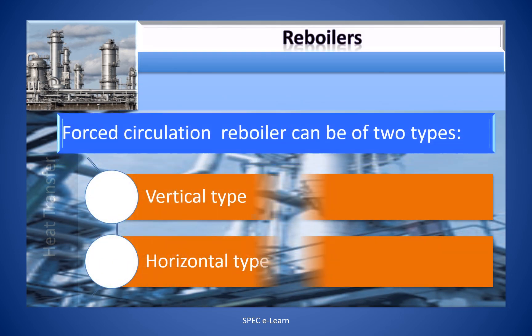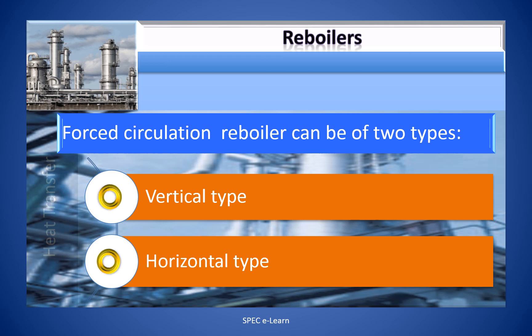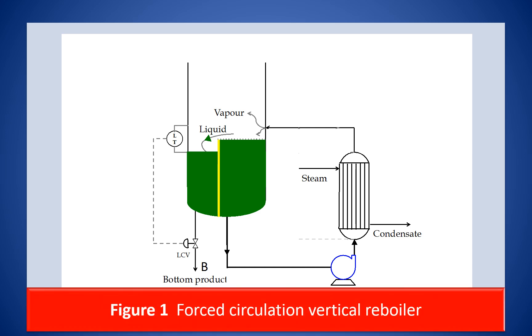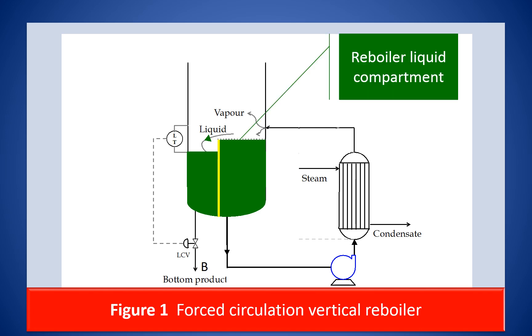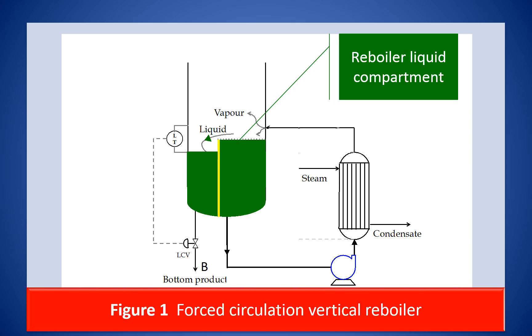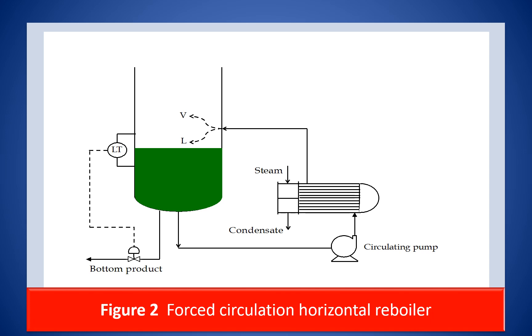Forced circulation reboilers can be of two types: 1. Vertical type, and 2. Horizontal type. The figure shown is an illustration of a forced circulation vertical reboiler. Note that, except for the pump and the elevation requirement, the internal design aspect is similar to the circulating thermosyphon vertical reboiler. There is also an illustration of a horizontal forced circulation reboiler, where the internal column arrangement for the reboiler circuit is the same as the thermosyphon horizontal reboiler.